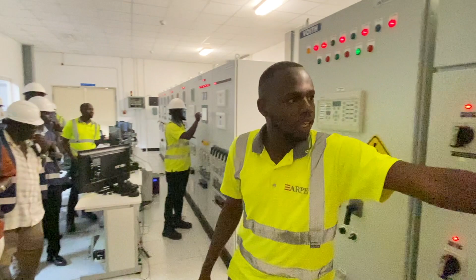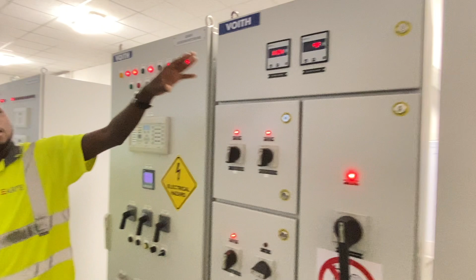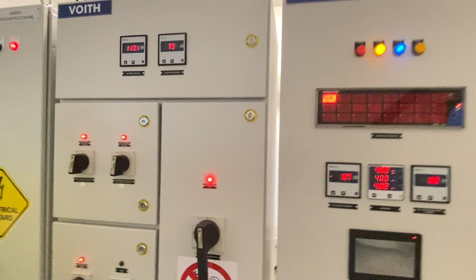In case we lose power from the grid, these systems have to keep running continuously. So we have batteries and a battery charger. This is the battery charger, and this is the DC distribution board. The batteries are always charged through this battery charger, which converts AC from our system into DC to charge the battery.